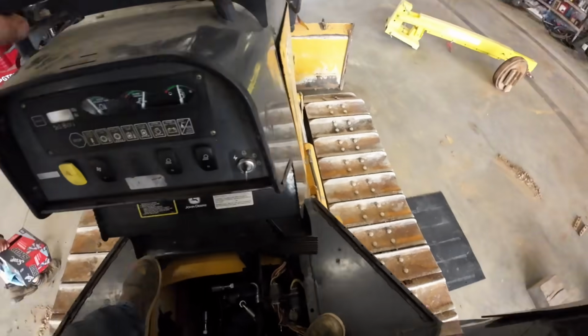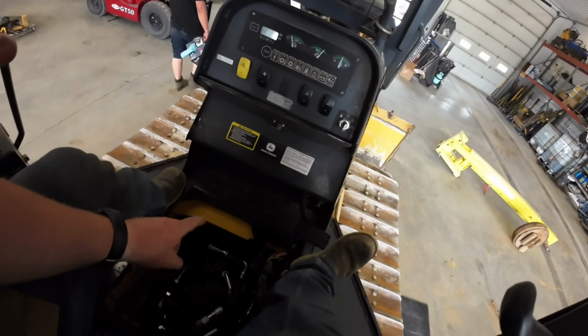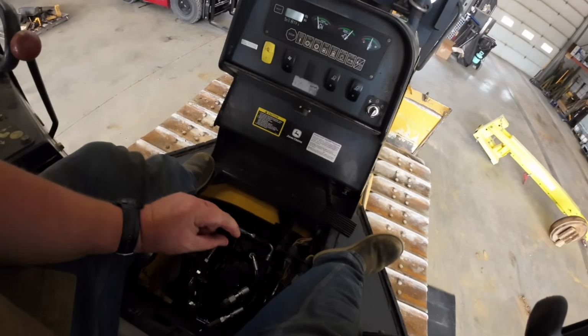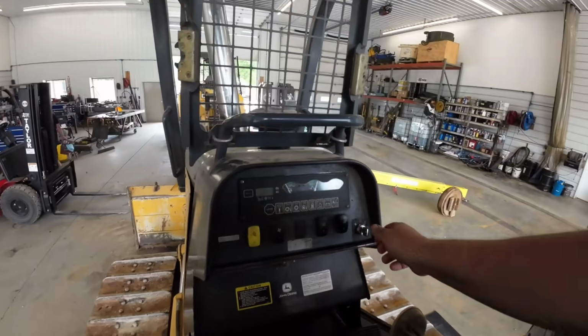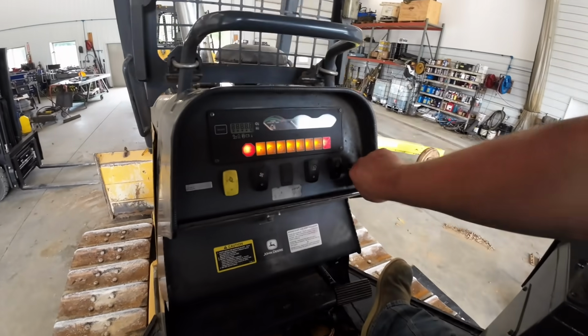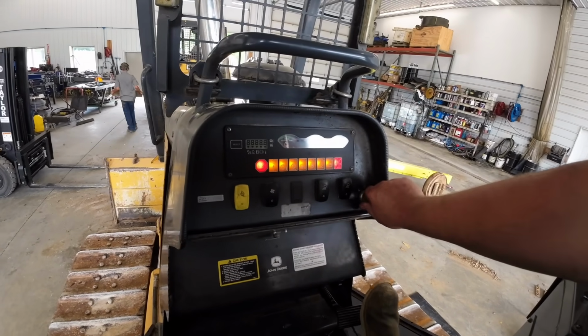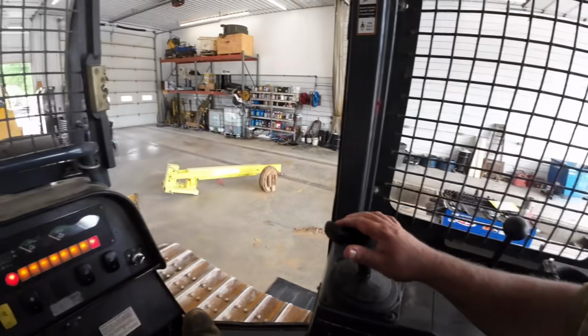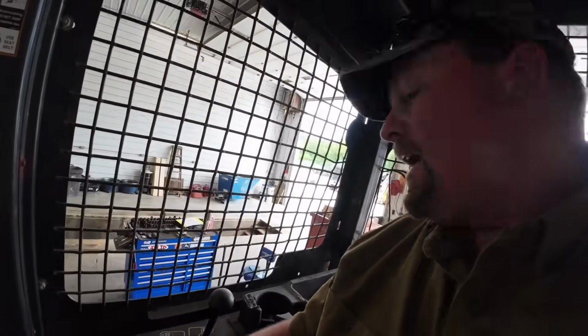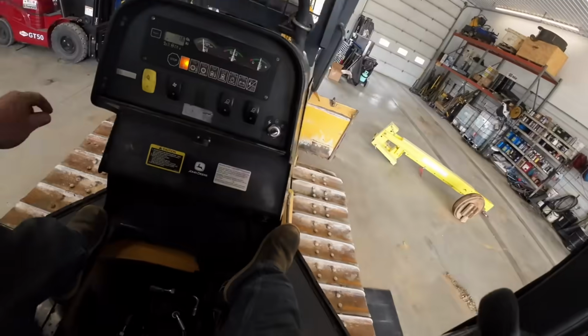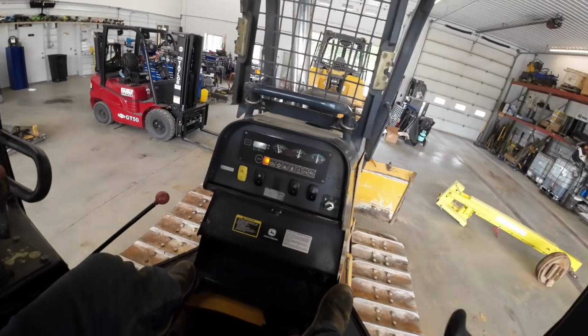Alright, we checked the front one too. The front one's okay, the back one was out of adjustment. That's the pump we just put in there. I'm guessing they may have not run it back through the test stand. Originally they had them all tested, they probably didn't run it back through the balances, so we've got to go out there again.